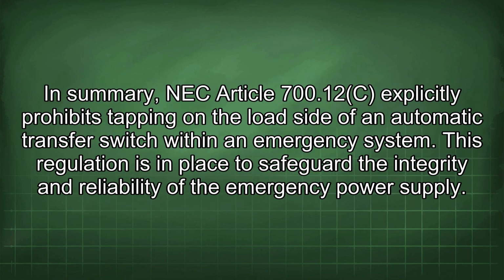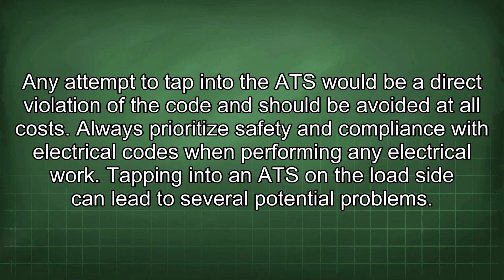In summary, NEC Article 700.12(C) explicitly prohibits tapping on the load side of an automatic transfer switch within an emergency system. This regulation is in place to safeguard the integrity and reliability of the emergency power supply. Any attempt to tap into the ATS would be a direct violation of the code and should be avoided at all costs. Always prioritize safety and compliance with the electrical codes when performing any electrical work.